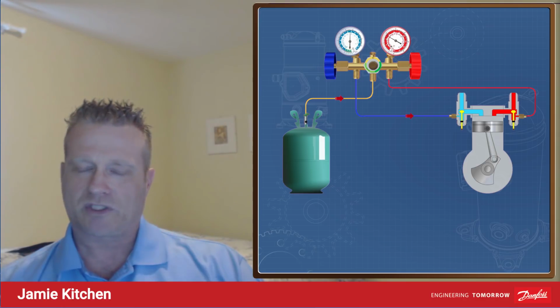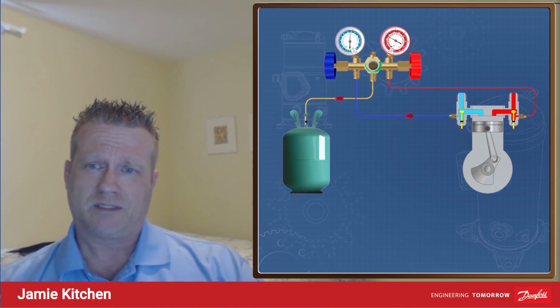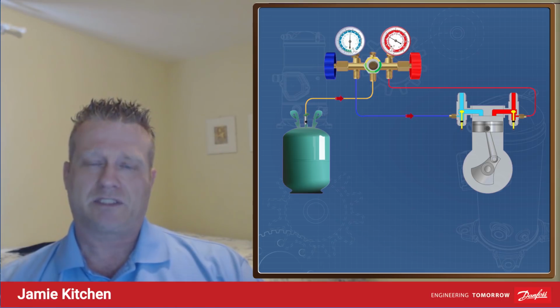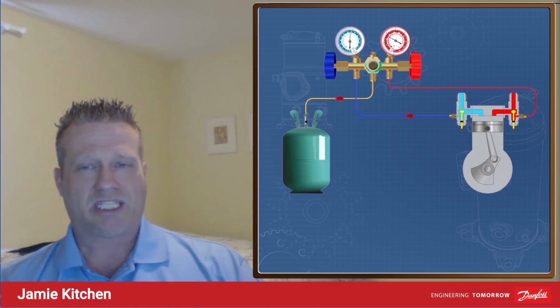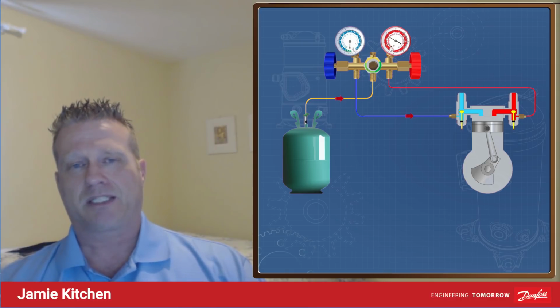If a system is overcharged, and I mean substantially overcharged, where's that refrigerant got to go? There's only so much volume inside of a system for the refrigerant. So in the off cycle, there's a much greater chance it's going to make its way back out to the compressor again.